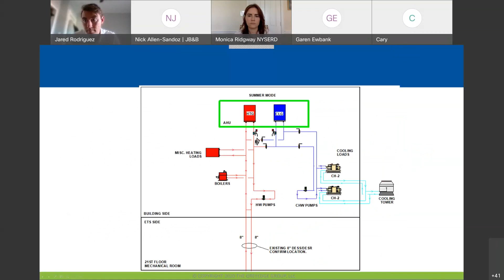Here's one of the outcomes as we move this: in summer mode, we keep those systems independent by closing these two valves, using the chiller and cooling tower. If we need simultaneous heating, we use our energy center or waste heat from the CHP to drive it - at that time we'll drive almost 100% of the heating load with the CHP.